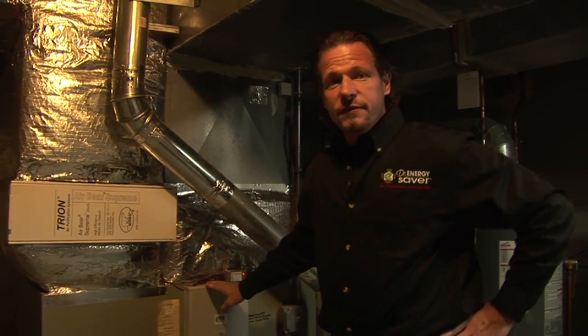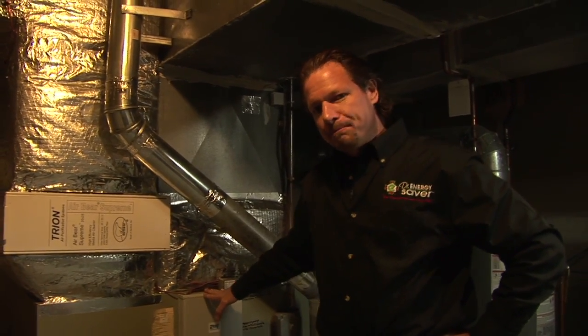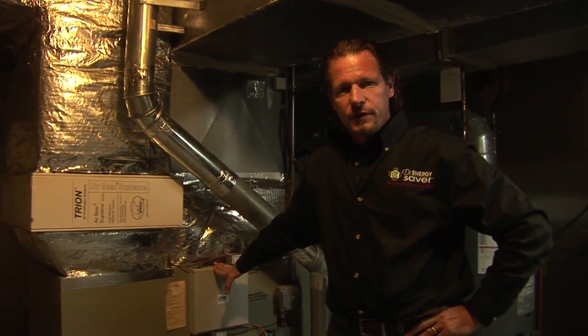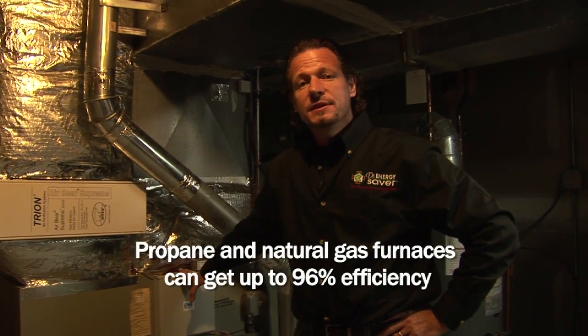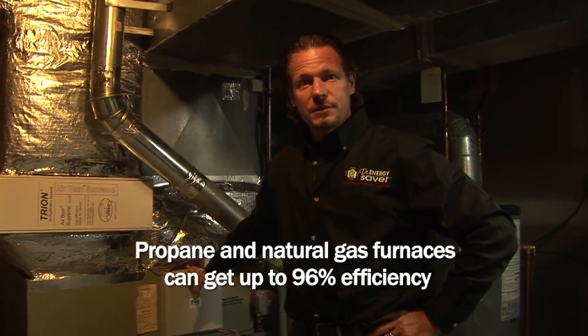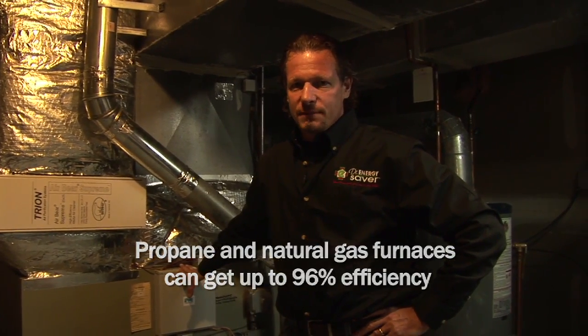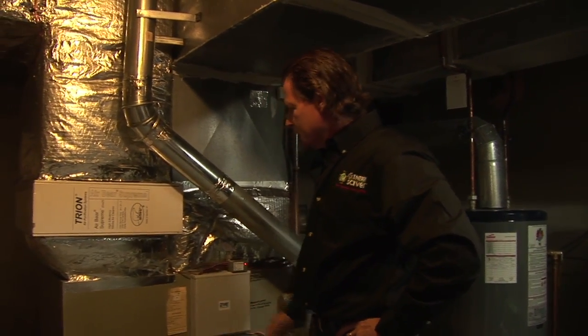The old oil furnace was 75% efficient. What that means is that 75% of the heat that you're paying for with that oil delivery gets to your house, and 25% of it goes up the chimney in the form of combustion gases. This new furnace is the highest efficiency you can get when it comes to oil furnaces, which is 87%. Now with propane equipment and natural gas equipment, you can get up to 96% efficient, which means only 4% of your heat that you paid for goes up the chimney. In any event, oil equipment is a little different. We don't get those efficiencies up into the 90s. We have 87% efficient. We have two zone valves, upstairs and downstairs.